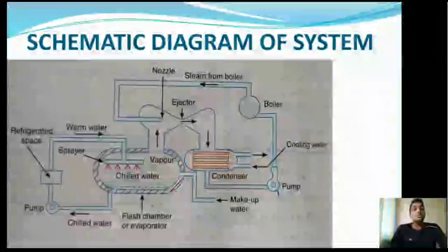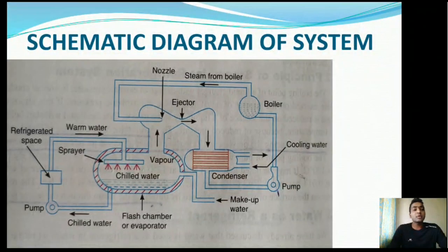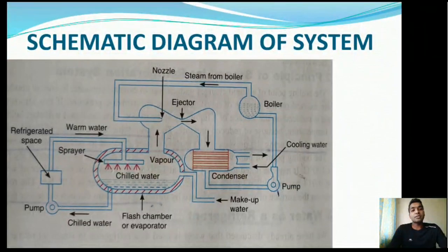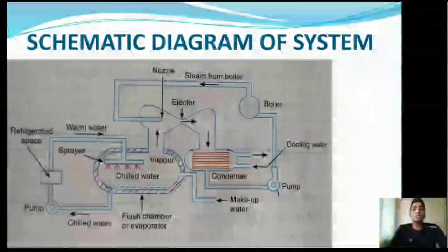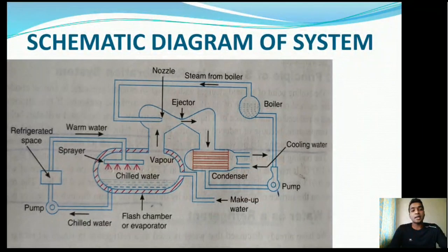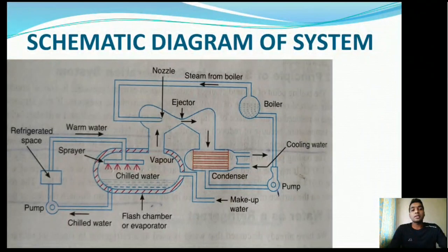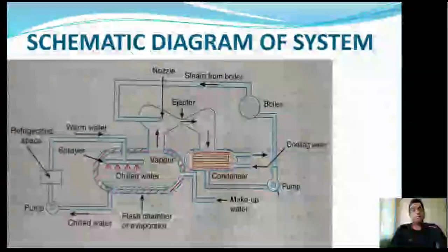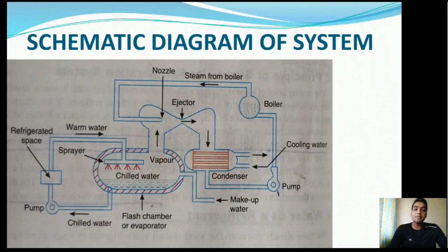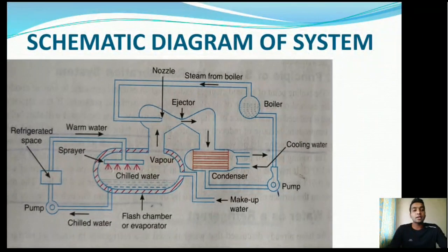Steam is sent from the boiler to the steam nozzle inside the ejector, where it expands to produce low-pressure, high-velocity steam at the nozzle exit. Due to this low pressure, water vapor is extracted from the flash chamber. At the throat of the ejector, the mixture of high-velocity steam and low-pressure water vapor undergoes compression, increasing its temperature and pressure. This mixture is then sent to the condenser.